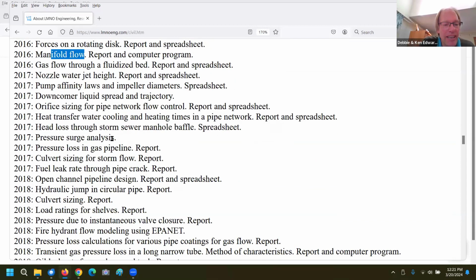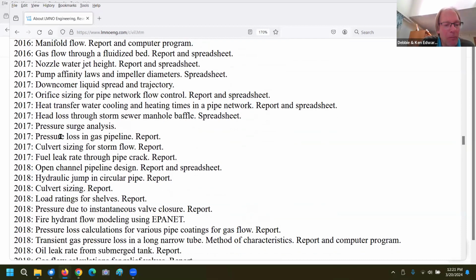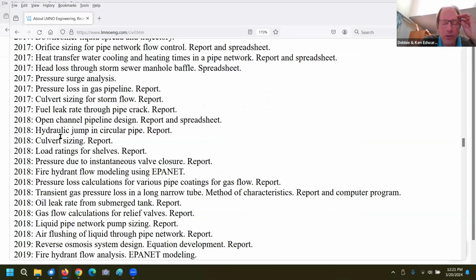Pressure surge, so we get into this now and then - water hammer. One of my favorite water hammer calcs, which I'll show you in a little bit, is just a super simple one. It just predicts worst case water hammer, as if you're shutting off a valve instantaneously. It gives you the worst case pressure, and that helps you determine the pressure in your pipe, and hence your pipe wall and maybe pipe material that you need.